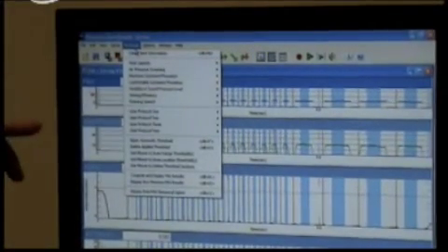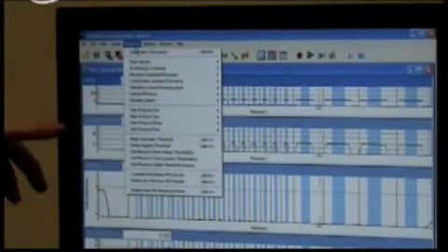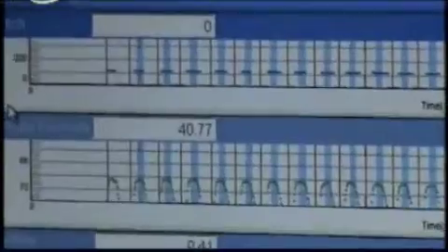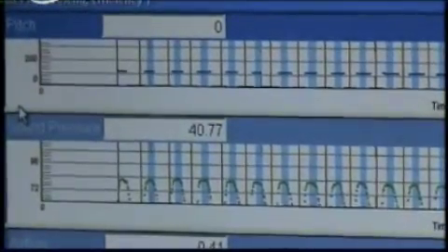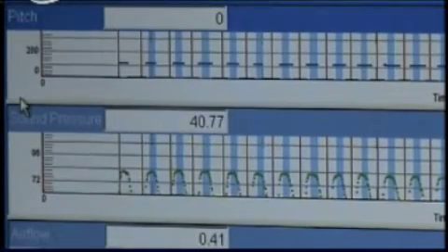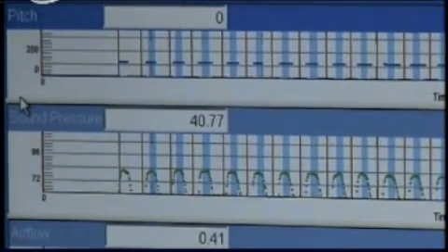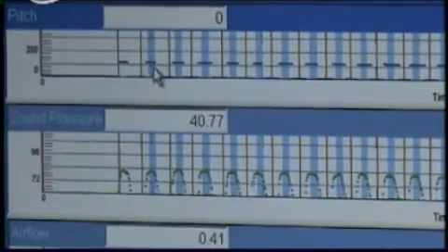So under these protocols here, I'm not going to go through these. This is something you're going to have to read up on a little bit in the manual, but user-defined protocols. You can create those. So you can say user protocol 1, new live input, and then collect the data, and then say, this is what I want. I want to do voicing efficiency on this one, and then it'll turn into a voicing efficiency. So I would stay away from that one.